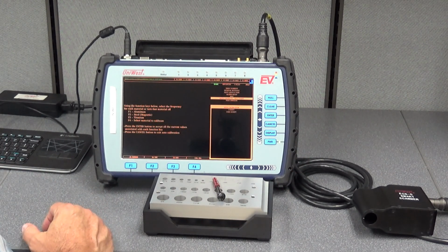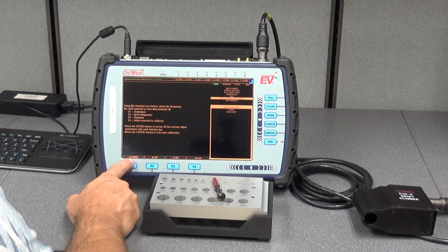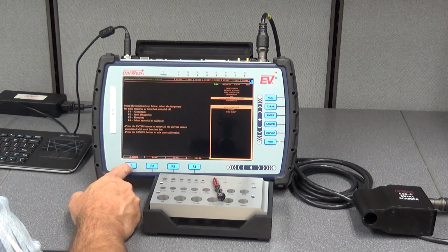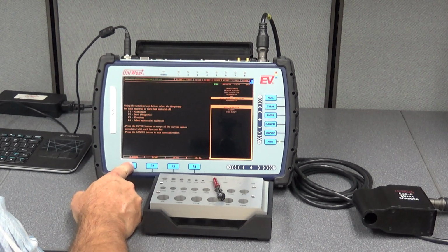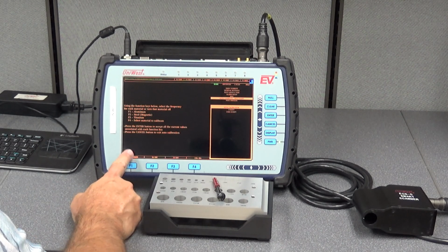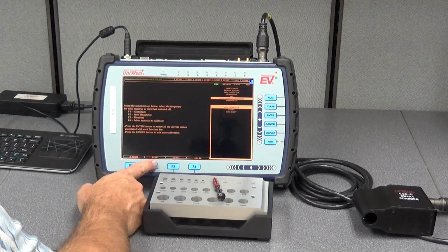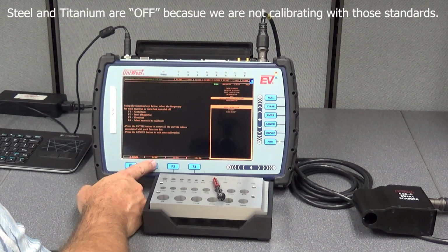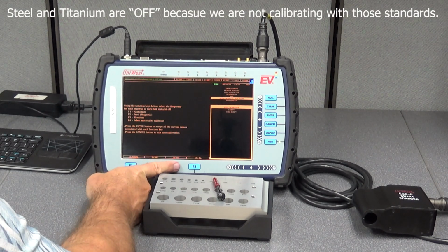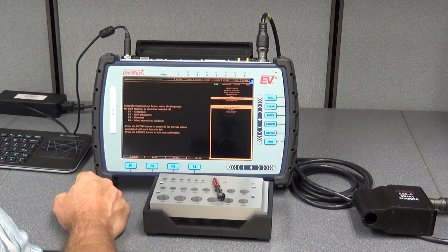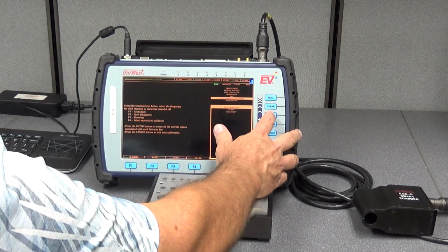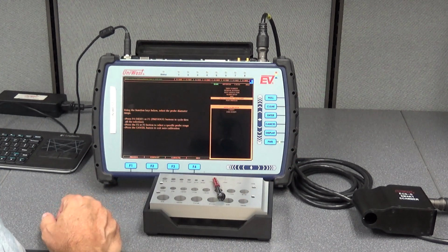Now we have to choose the frequency for the different materials. So for aluminum, we're going to keep it at 500 kilohertz, but we could choose aluminum off, aluminum 200 kilohertz, aluminum 500 kilohertz. So we'll keep it at 500 kilohertz. Steel, the frequency is off. Titanium, the frequency is off. And we're going to press the enter button to accept and move on.